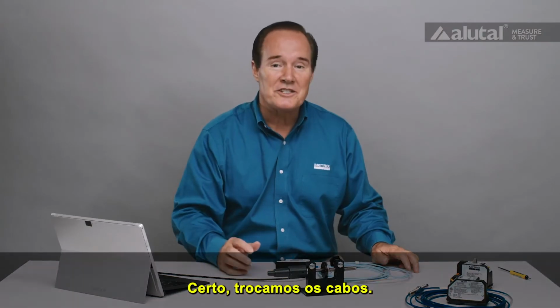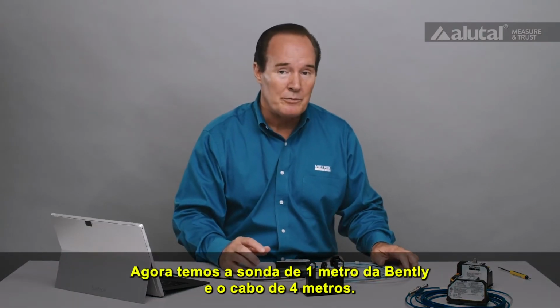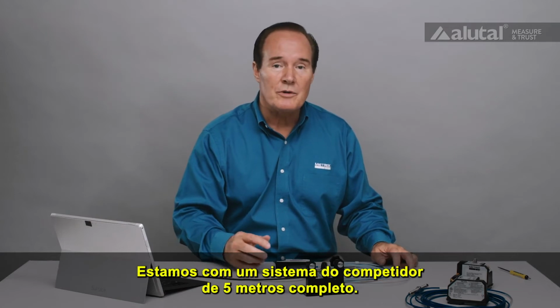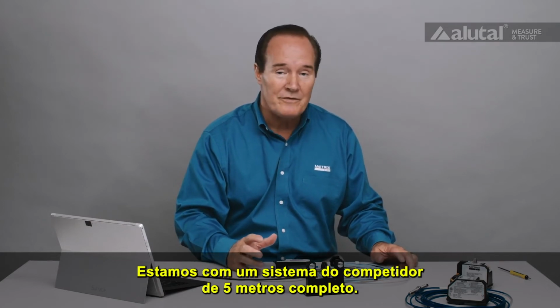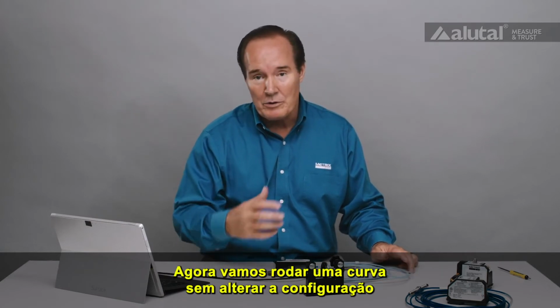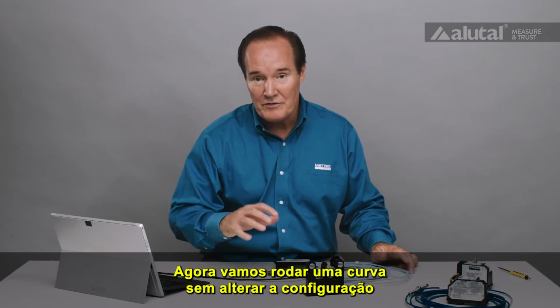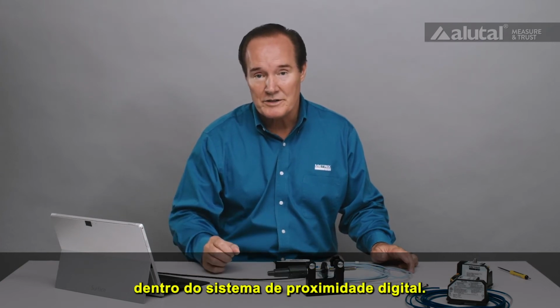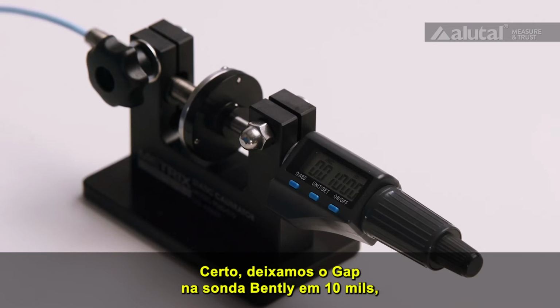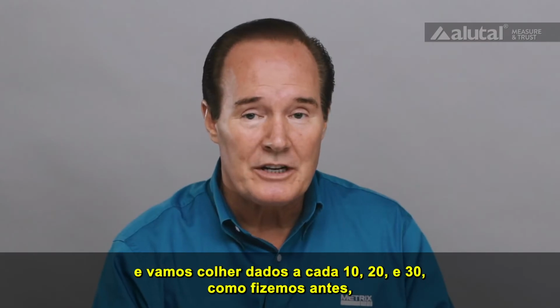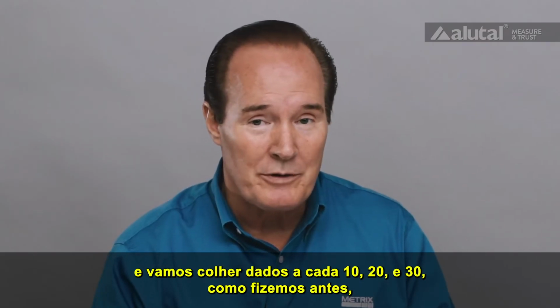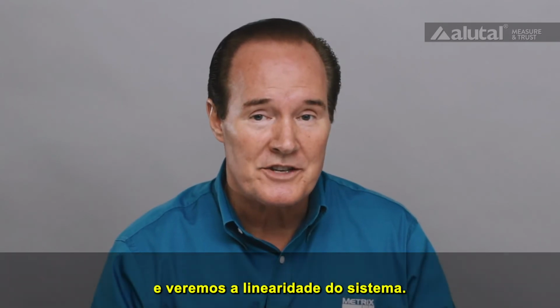All right, we've changed the setup, and now we have the Bently 1 meter probe and 4 meter cable. So we have a full competitive 5 meter system. Now we're going to run a curve on it without changing the configuration inside the digital proximity system. All right, we've gapped the Bently probe at 10 mils, and we'll take data every 10, 20, and 30 just like we did before, and we'll check the linearity of the system.